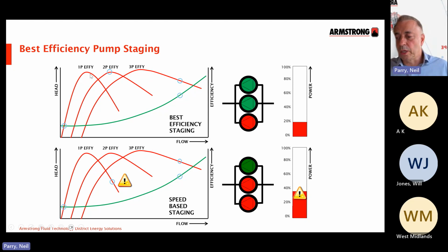Now, if you control these pumps or stage the pumps using the BMS, what tends to happen is you'll run pump number 1 to say 95% of its speed, and then bring in pump number 2, run that up to 95%, and then bring in pump number 3. Well, you can see here, if we're running to 95%, all this time this first pump is running at a really poor efficiency point.